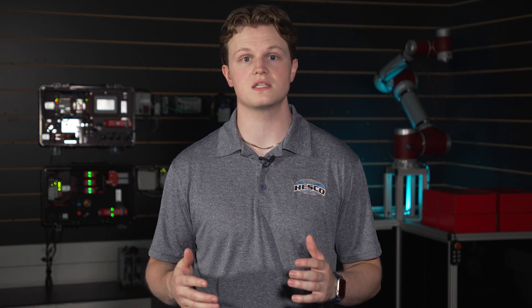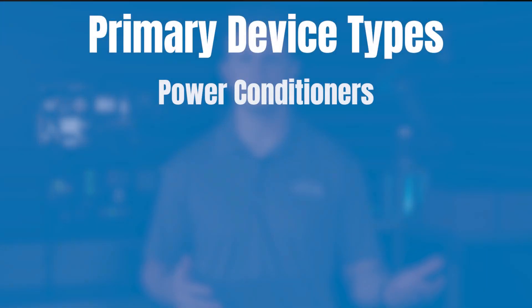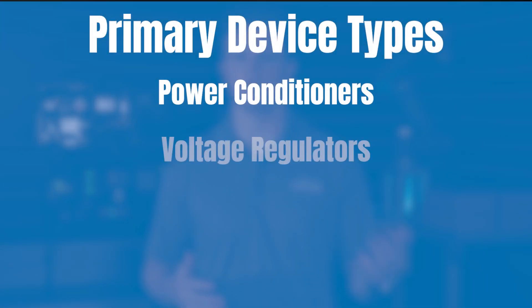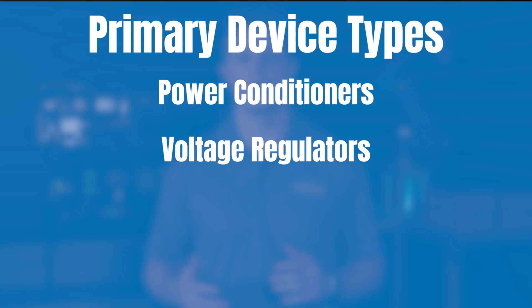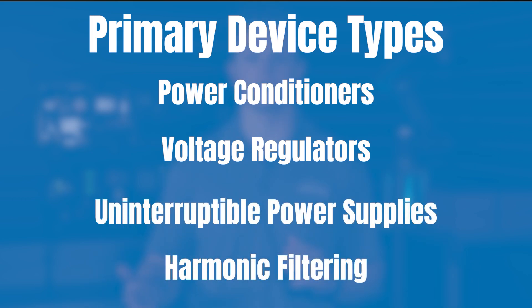While there is no one-fit solution, dirty power can be converted to clean power using devices such as power conditioners, voltage regulators, uninterruptible power supplies, and harmonic filtering, depending on the root cause.